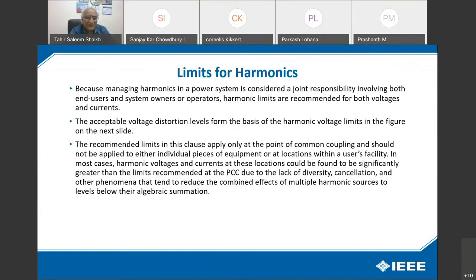In most cases, harmonic voltage and currents at these locations could be found to be significantly greater than the limits recommended at the PCC due to the lack of diversity, cancellation, and other phenomena that tend to reduce the combined effects of multiple harmonic sources to levels below their algebraic summation.